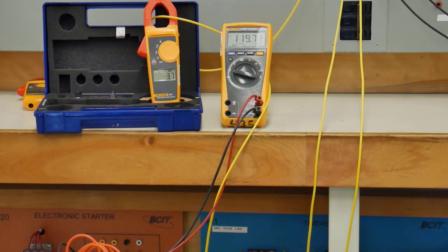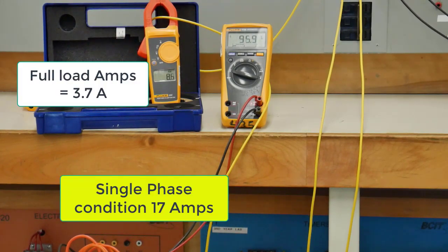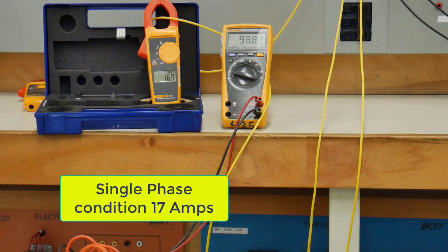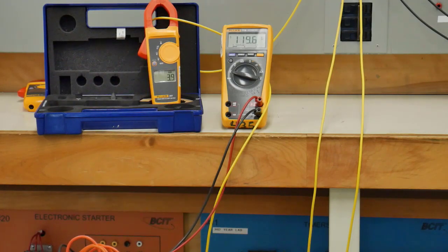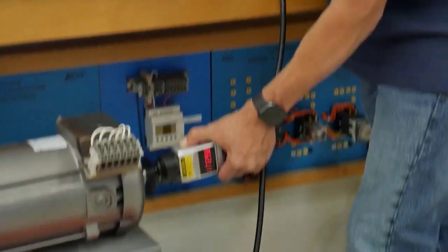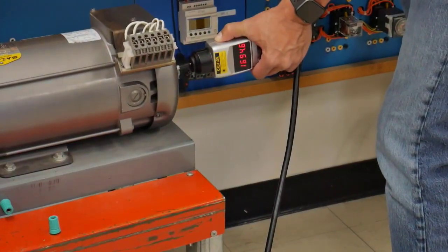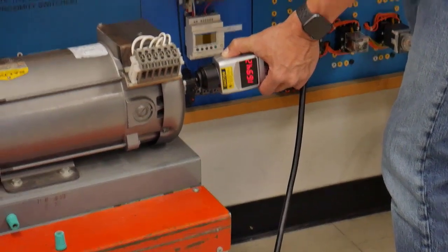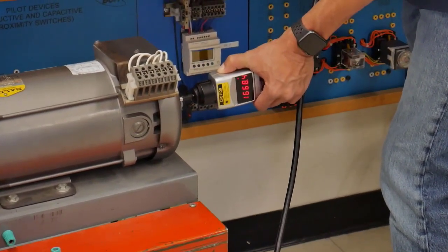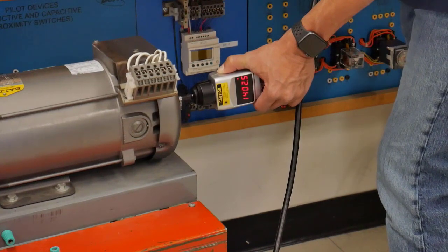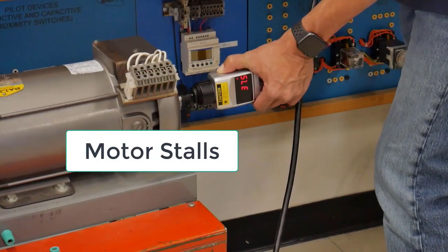Now let's create our single phase condition. As you can tell, the current jumped all the way up to 17 amps, so it started rising quite high. Now let's have a look at the same single phasing. We'll make the fully loaded single phasing condition occur again, and let's watch the RPM. It's dropping down all the way to a stall condition.